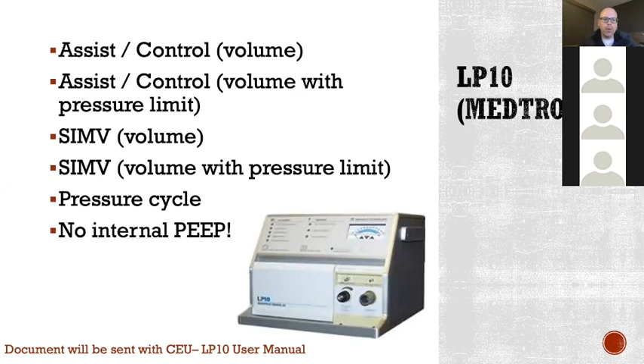This is what the front of that ventilator looks like. It's pretty easy to set up if we needed to actually set up settings on it. First, you're going to dial what mode you want. So let's say we're going to do SIMV. You would just dial SIMV right here. Let me see if I can draw on it. No, that didn't work. Okay, so right here you would do SIMV. Then you have your volume. We would just set the volume. This volume is per breath, so it's in decimals. So 0.4 would be 400 cc's per breath. So we just dial whatever breath volume we want.